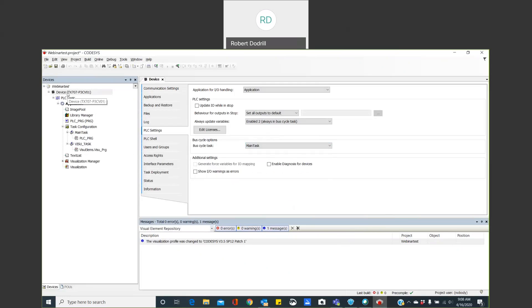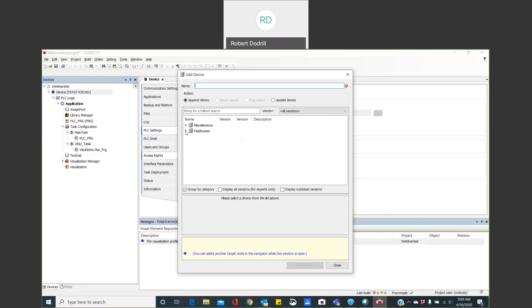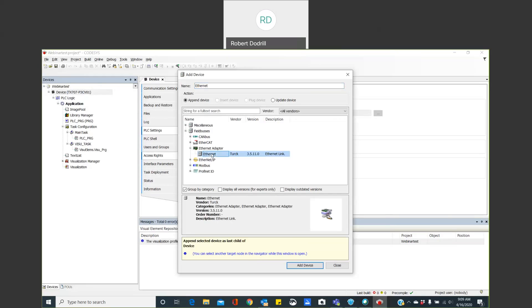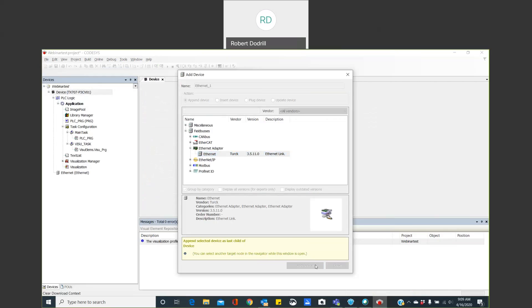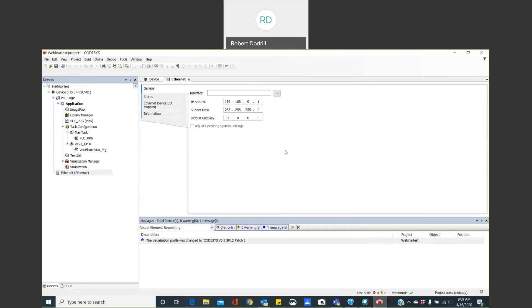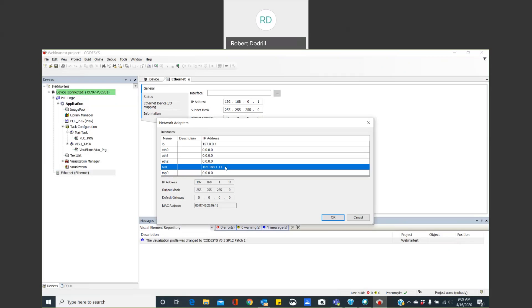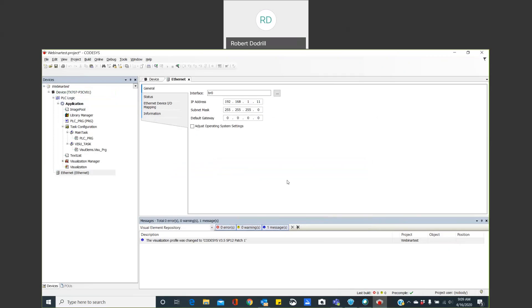So the first thing I want to add under my device menu is I want to right click on that, and I'm going to add a device because I want to use Ethernet as my field bus. The first thing I need to add is my Ethernet driver from my PLC out to devices. So I have the option. I can either double click on this or I can click add device. So once it's loaded in this side, now I want to open my Ethernet tab. I need to find the driver that's in my PLC. So I'm going to click this lookup button. And in my case, I know that this is the IP address of my panel. So I'm going to use this driver right here, and I'm going to say OK. And it automatically loads the IP address of my panel, and I'm prepared to take the next step.